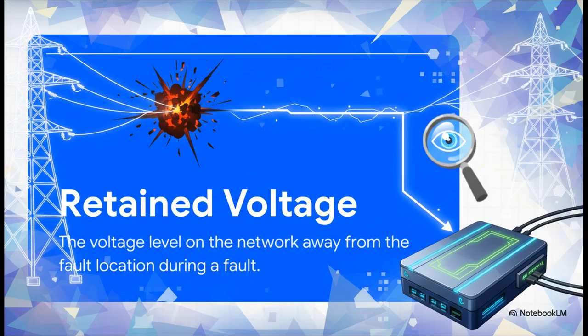So when a fault happens, the voltage right at that spot collapses to zero. But everywhere else on the network, the voltage just dips. That level it dips to is the retained voltage. And for an inverter's control system, that's the most important signal it's looking at.